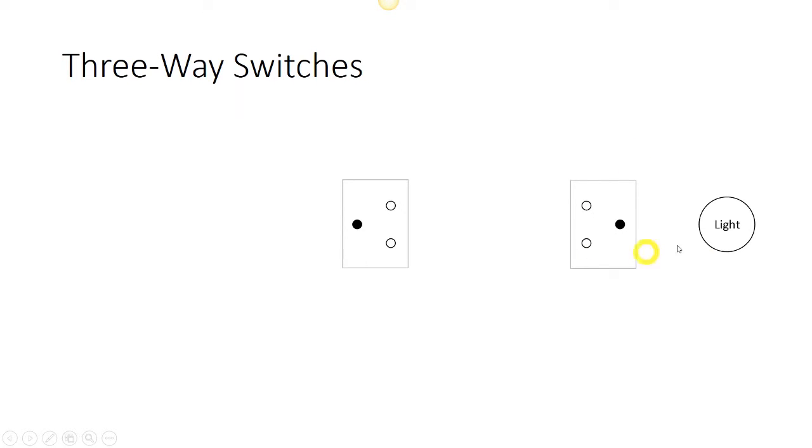This switch is actually very close to this light, so for that reason, on this switch, I'm going to connect power to it. And because a common has 2 functions, the second function being sending a switched signal to the light, I'm going to send my other common straight to my light. So I've got my 2 commons connected.